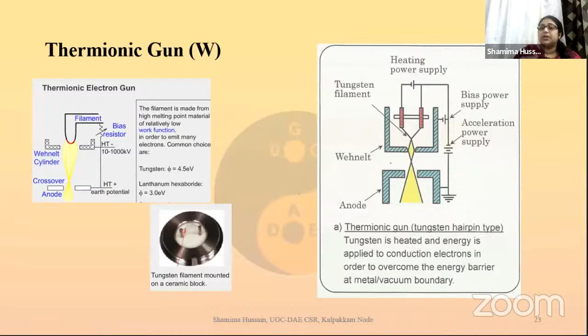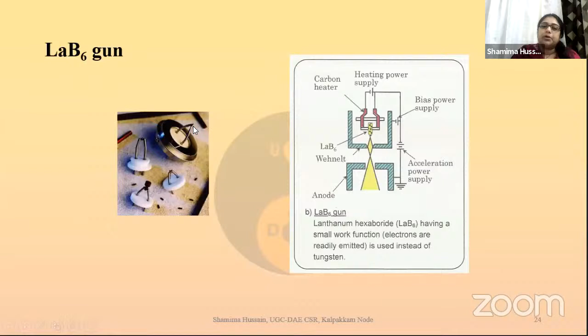LaB6 was another such thing. And there also, instead of tungsten, we would have this LaB6, lanthanum hexaboride. We would have a compatible heater. And again the Wehnelt cup, then we have the anode, and here we are talking of this acceleration power supply. This is what we had earlier also. But in case of tungsten, it was not much required, because tungsten being a metal used to emit a lot of electrons. Whereas in case of LaB6, sometimes we used to have difficulty, and hence we needed this acceleration pretty badly. And that is the reason we had better magnification, better resolution with the LaB6 filaments. Here also, just see, this is how it actually looks, like a kind of V, a point should be there, right?